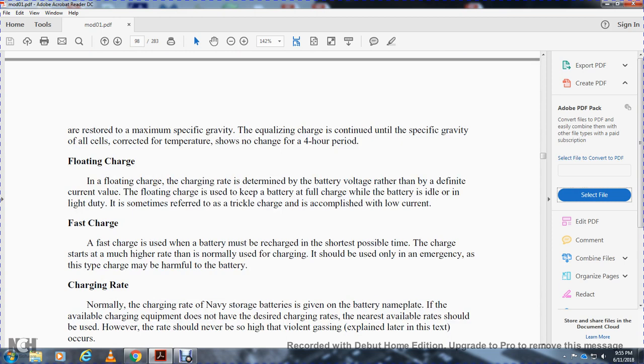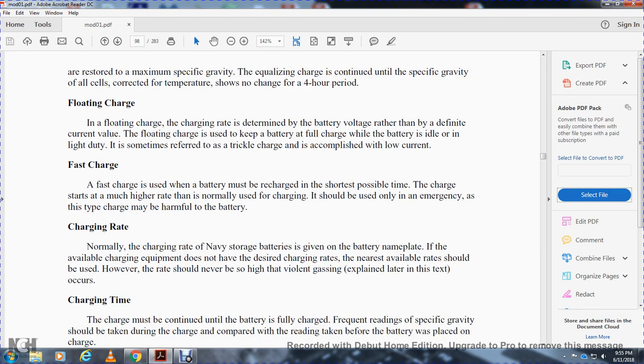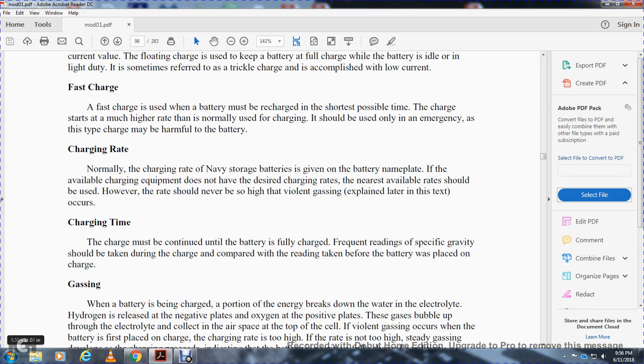Floating charge is a charge rate determined by the voltage rather than by a defined current value; it is used to keep the battery at full charge while the battery is idle or on light duty — sometimes referred to as trickle charge. Fast charge is a charge given at a much higher rate than normal to recharge the battery in the shortest possible time; it should only be used in emergencies as this type of charge is harmful to the battery. The charging rate for storage batteries is normally given on the battery nameplate.